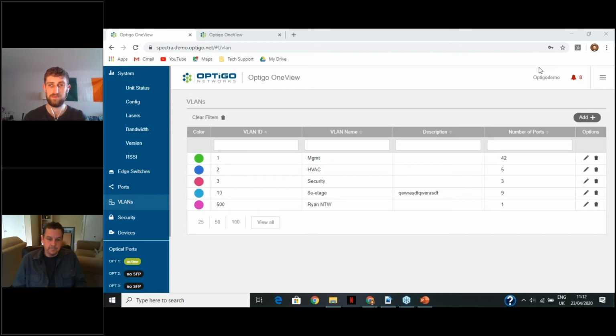But outside of that, as you start putting in these OT networks, hopefully you're putting it in as an OT system, which means many other services are going to be riding on your network, specifically HVAC, maybe security in terms of surveillance, access control, lighting, energy meters. The list goes on, depending on the configuration of the site. Here is a way that we can segregate that traffic by using VLANs separately. So we're going to take all HVAC traffic and make it blue. We're going to set it on VLAN 200, maybe, and then continue on from there.